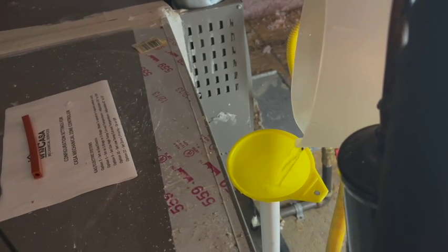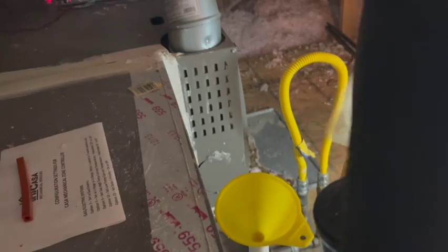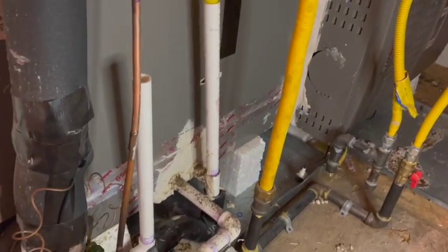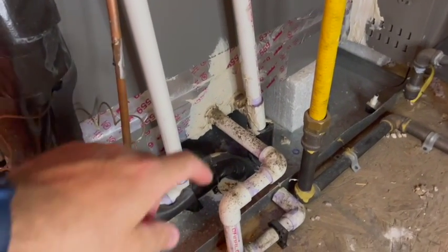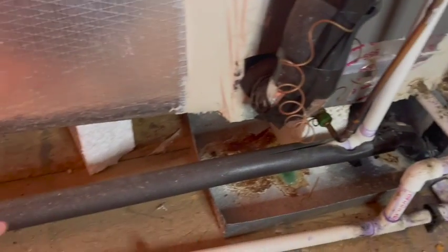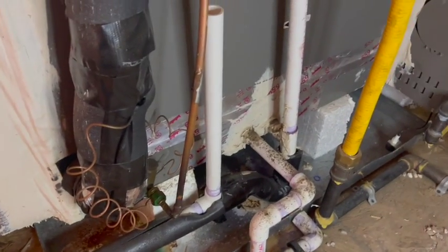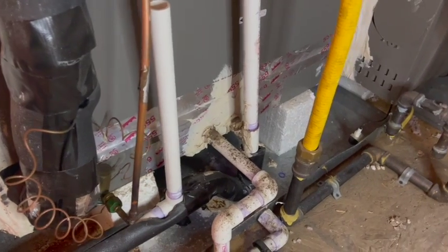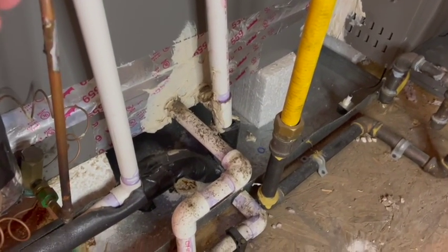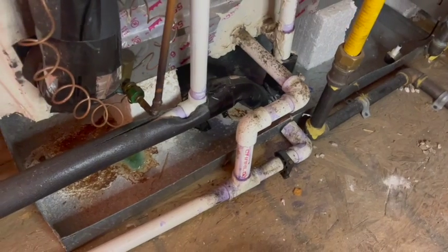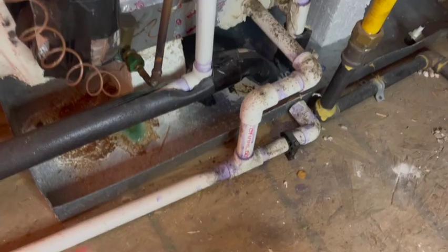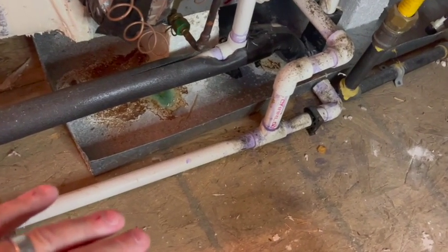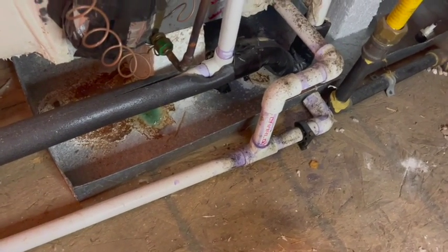Now this is important because air conditioners, especially in Texas, it's warm. Air conditioners can produce 20 gallons of condensation in a single day. That 20 gallons is going to be coming through this line and draining out to your main drain. If that's clogged, you're now going to have 20 gallons of water trying to go through your secondary. And if that can't keep up, then it's going to spill out into your pan, and it's going to spill out onto your attic space or wherever your system is.